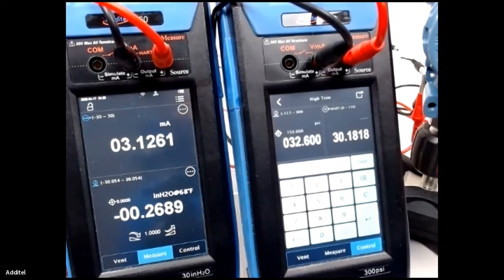So we're actually pressurizing the transmitter right now. It's going to go up to 150 PSI. Then we can zero the data at both points, at the top and the bottom. But this is probably something you would do after you run the calibration. I was messing around with this earlier, and the transmitter is really pretty close to right on. We'll see if it's right on at 150, but we'll let it pressurize up. As you guys can see, it's pretty quick to get to pressure.